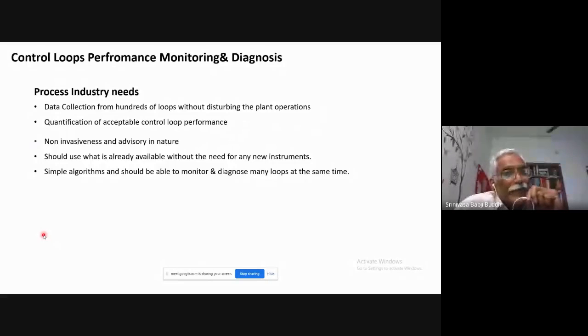Then this control loop performance monitoring and diagnosis should be advisory in nature. You should not do any closed loop automatic corrections. It should be only advisory, and non-invasive. It should not disturb or make any changes in the process operations. And also they do not want to invest in any new additional equipment or instruments for the sake of control loop performance monitoring. Whatever is already installed and available, only those equipment and measurements need to be used in this monitoring and diagnosis. And the computation algorithms being used should be simple, and the loop performance monitoring application should be able to collect the data and analyze and diagnose many loops at a time.